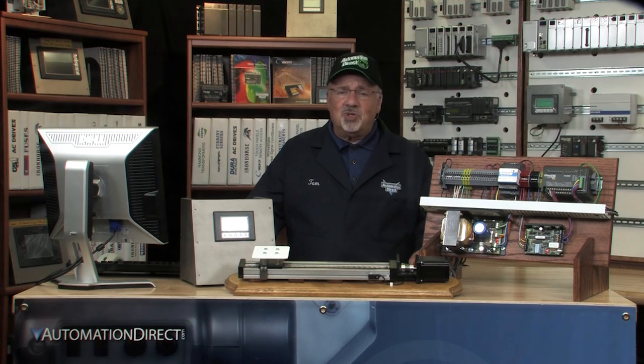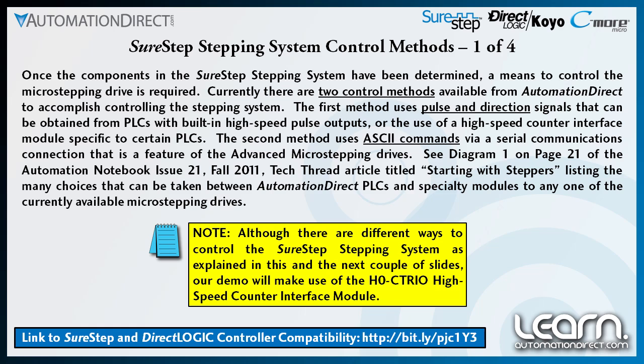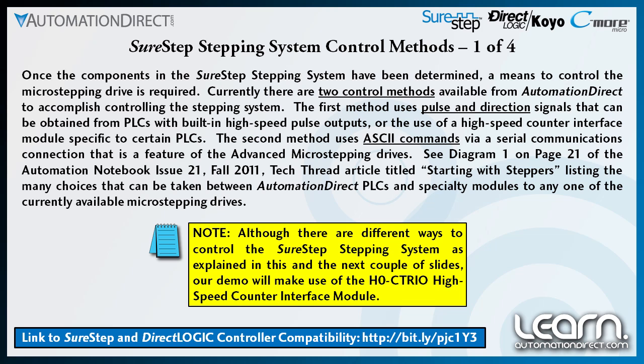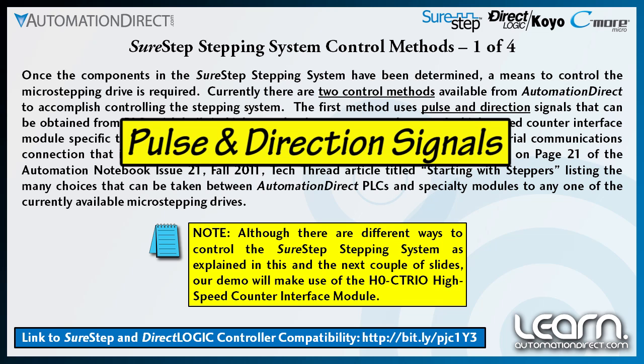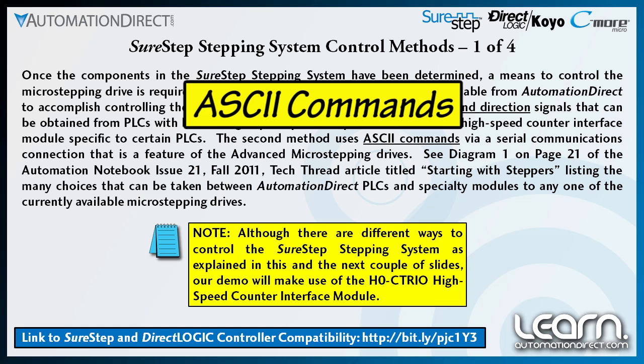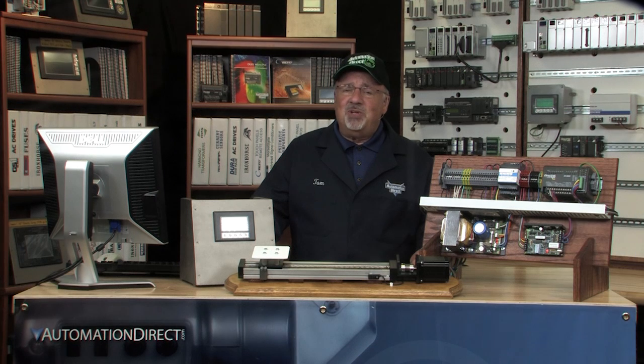Once I determined the particular SureStep components I would need in my motion control demonstration, I next had to decide on how I wanted to control the stepping system. There are currently two methods available for controlling the stepping system. The first method uses pulse and direction signals, which can be obtained from AutomationDirect's PLCs with built-in high speed pulse outputs or by using a high speed counter interface module that works with certain PLCs. The second method uses ASCII commands by way of a serial communications connection, which is a feature of the advanced micro-stepping drives.